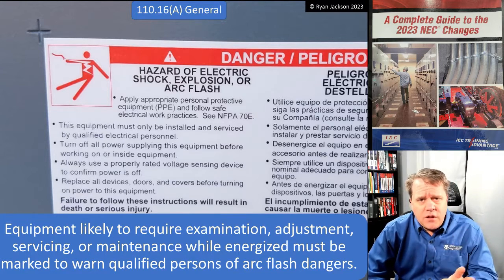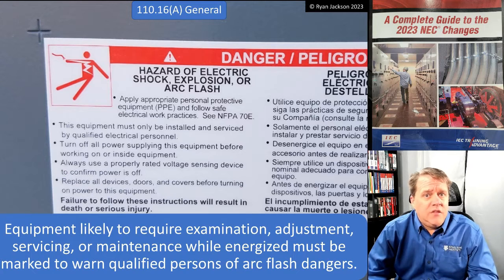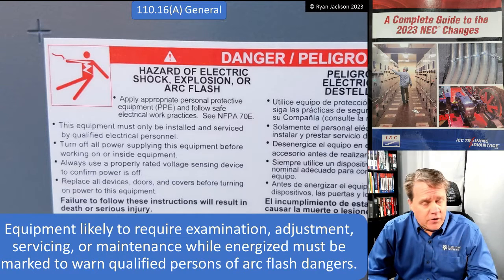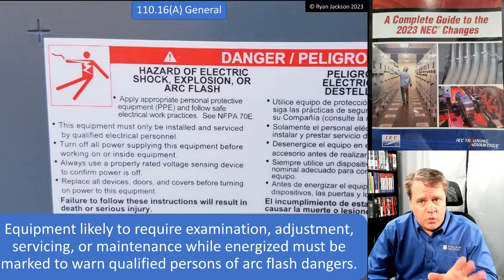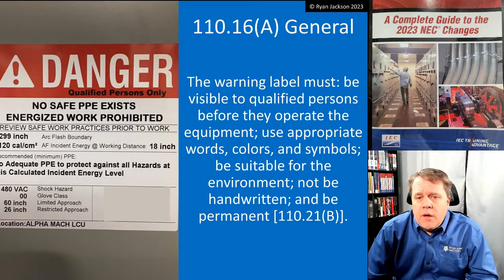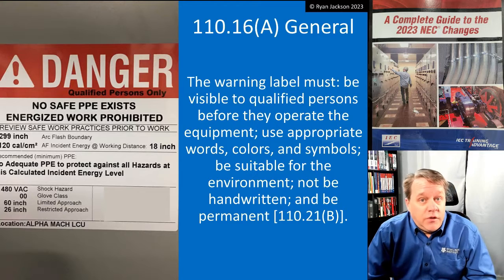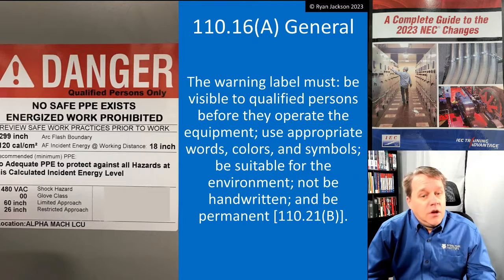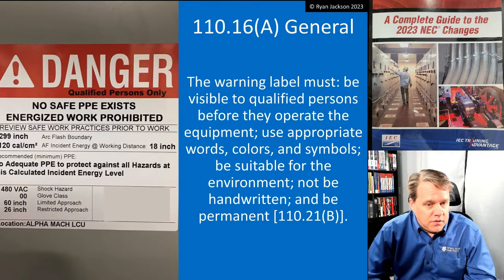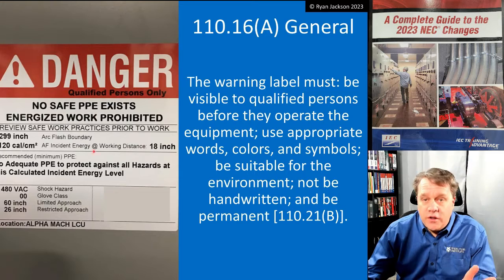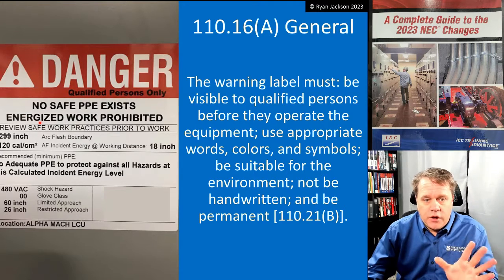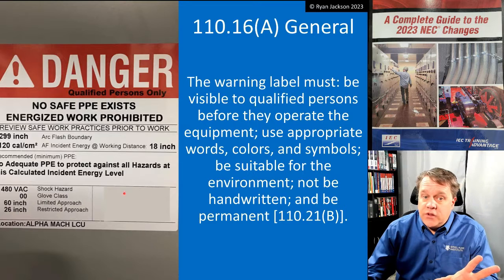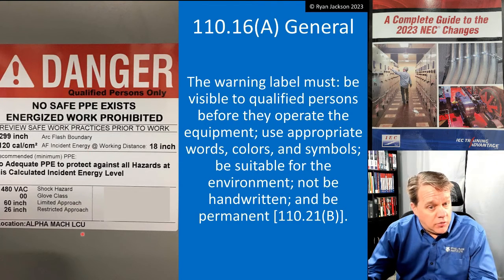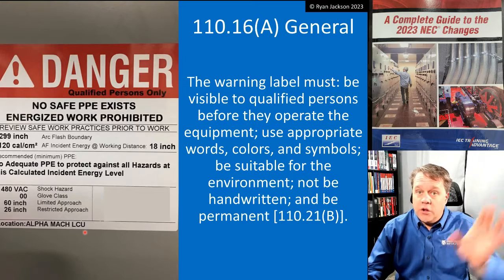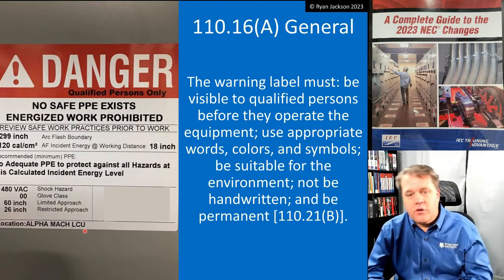We got to have a warning to remind people that when things go wrong in our industry, they go very wrong, very fast. All right, so warning, arc flash. Now the warning label must be visible to qualified persons before they operate the equipment. It has to use appropriate words, colors, and symbols, be suitable for the environment, not be handwritten, has to be permanent. All right, so some sort of a warning sticker like this, right? Some arc flash warning. So again, this sticker here has more information than the code requires. Okay, the code just requires warning, arc flash, suitable colors, suitable words, right? All of that.